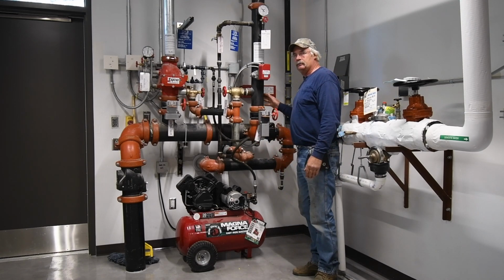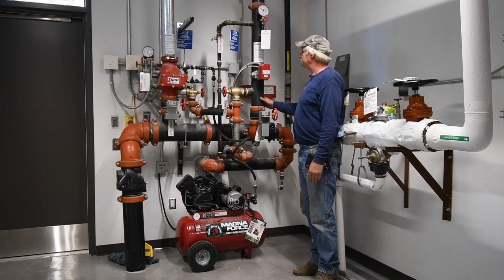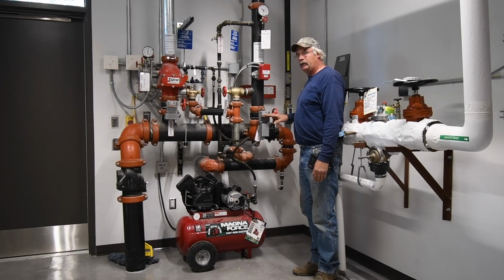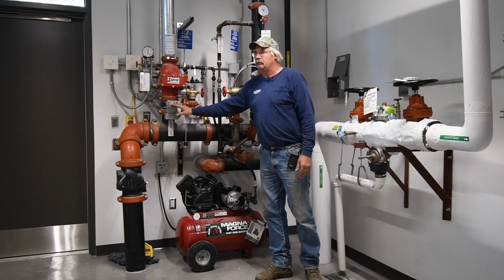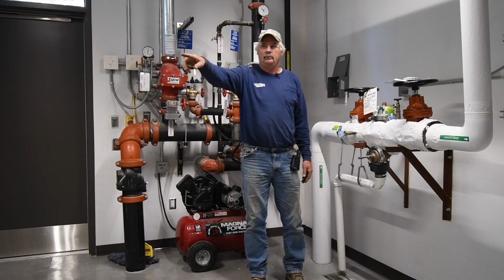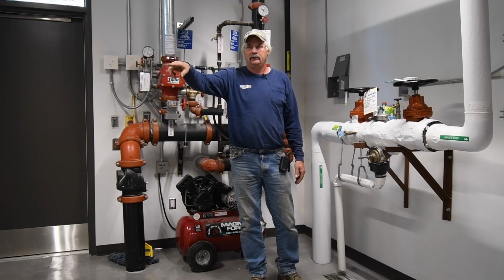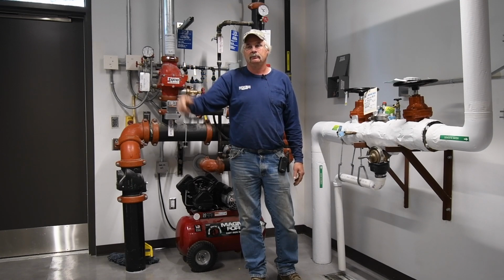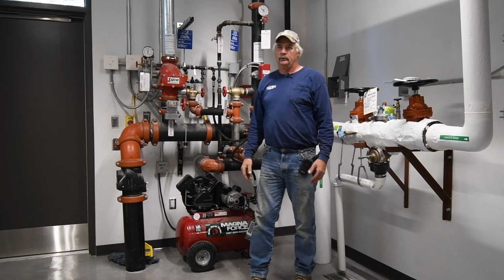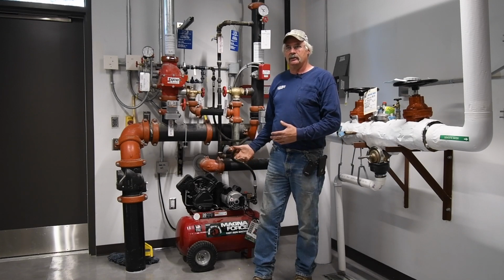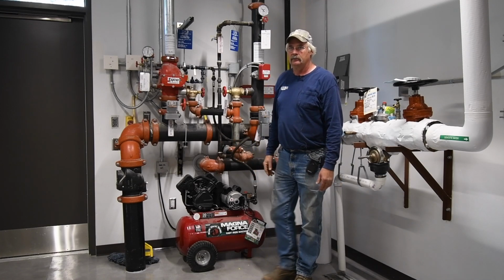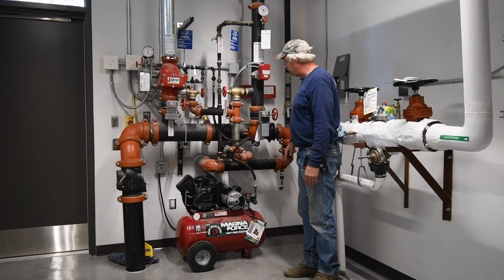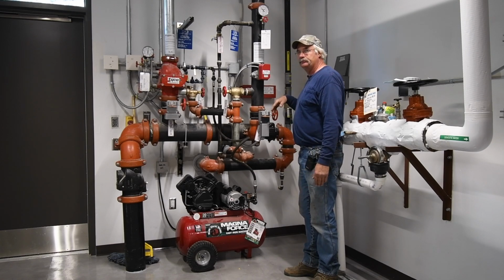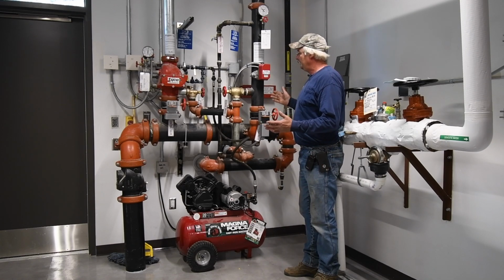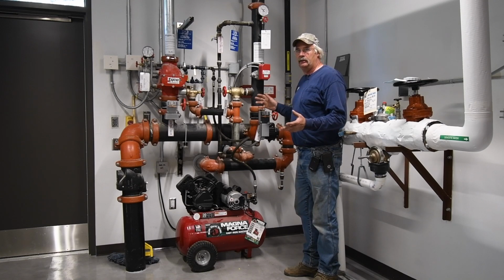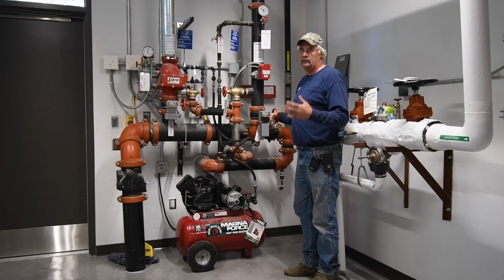So basically what we have here is a wet system. Right now the control valves are both shut off due to the fact that the fire alarm panel has not been finished and it's not a monitored system. So per code, per state law, we can't leave systems on until they're monitored, if that makes sense. But basically on a wet system, it's pretty much self-sufficient.